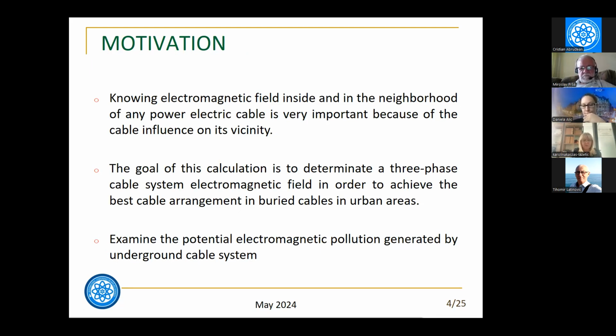High voltage supplying cables should be buried in special corridors constructed for these cables only, or in already existing corridors for telecommunication systems and water pipeline systems, especially in the case when high voltage cables are positioned close to any other installation. It is crucial to be familiar with the electromagnetic field produced by the cables and the influence of the field on the neighboring systems. In order to examine the high voltage cable shielding efficiency, at first we examined the electromagnetic field of a real standardized single high voltage cable, and after that the electromagnetic field distribution of a three-phase high voltage power transmission system consisting of three single core high voltage cables.